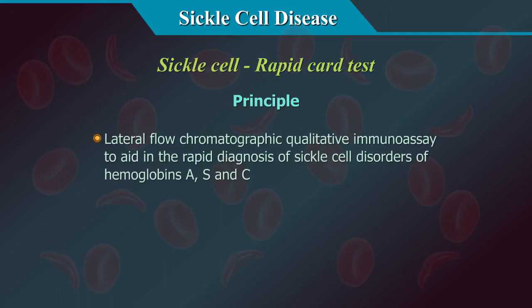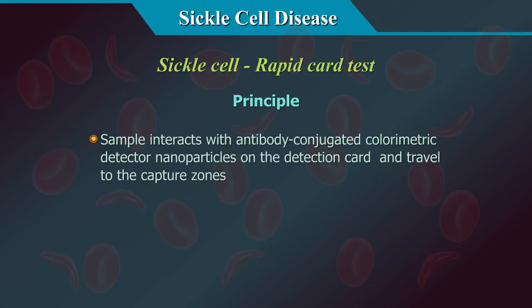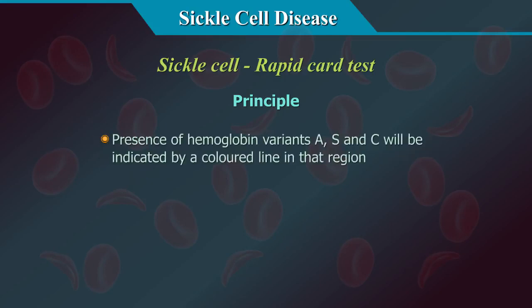The sickle scan rapid card test is a lateral flow chromatographic qualitative immunoassay to aid in the rapid diagnosis of sickle cell disorders of haemoglobins A, S, and C. A small amount of blood is placed into the buffer-loaded pre-treatment module to release haemoglobin by lysing the erythrocytes. The sample interacts with antibody-conjugated colorimetric detector nanoparticles on the detection card and travels to the capture zones. The presence of haemoglobin variants A, S, and C will be indicated by a coloured line in that region.